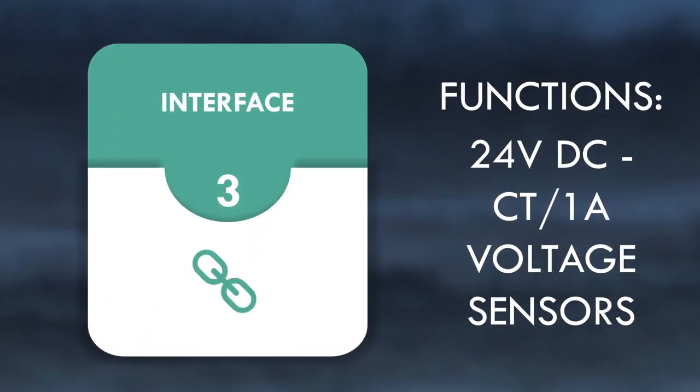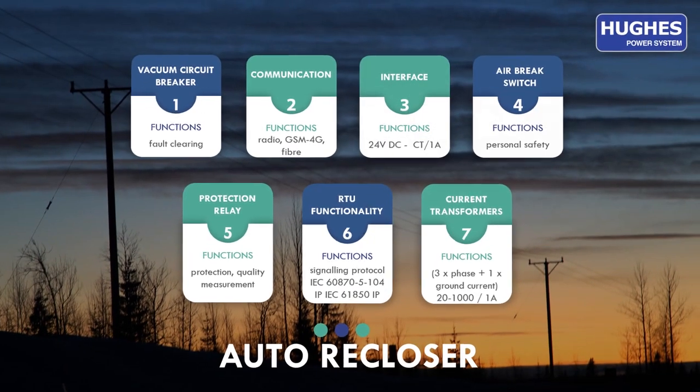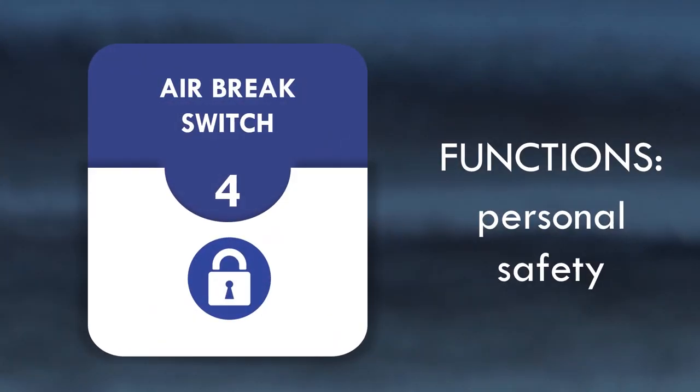Interface is basically a connecting cable between protection relay and a switch module, 24V DC operation, 1A current transformers and voltage sensors, and integrated air break switch.